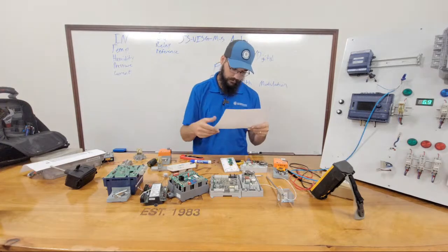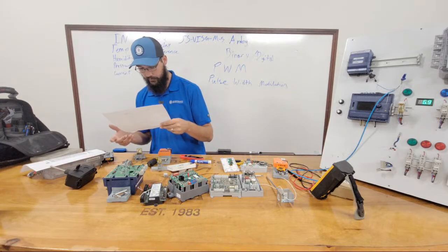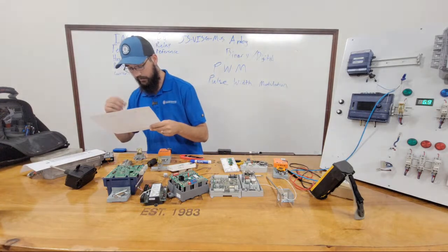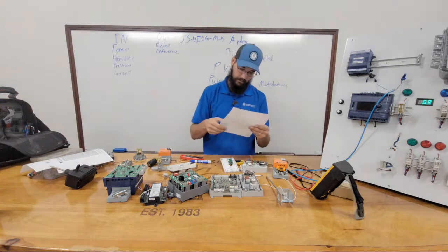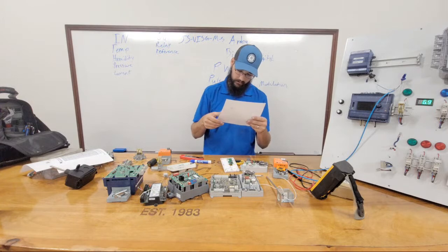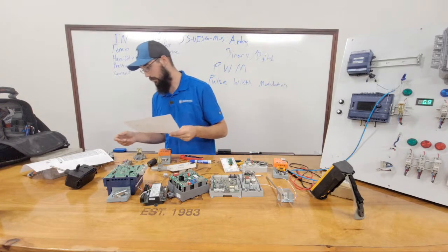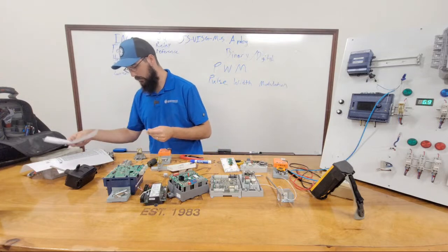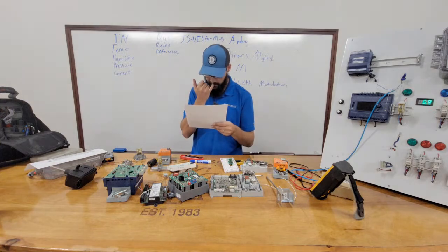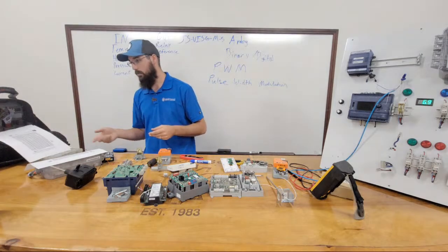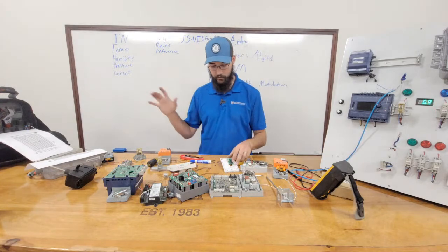So, for example, 111 degrees on a type 2 is 4,561 ohms, whereas a type 3 is 4,847 ohms. And those 300 ohms is a significant change in temperature. So that's going to throw off your calibration if you're using the wrong chart.